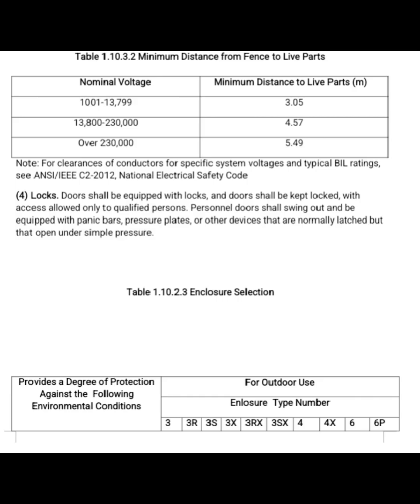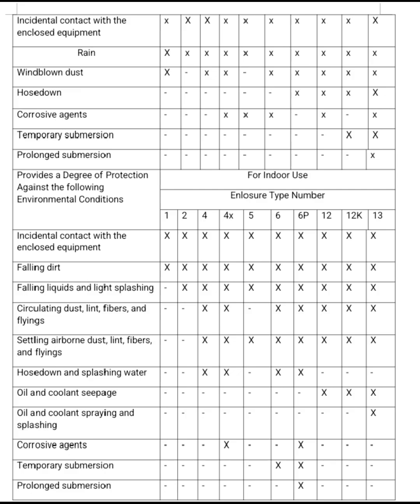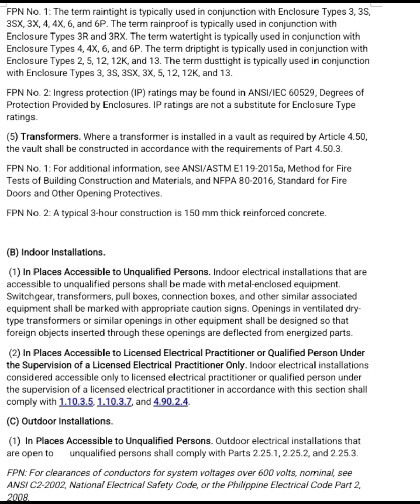Table 1.10.2.3 Enclosure Selection provides a degree of protection against the following environmental conditions. Number 5. Transformers. Where a transformer is installed in a vault as required by Article 4.50, the vault shall be constructed in accordance with the requirements of Part 4.50.3.